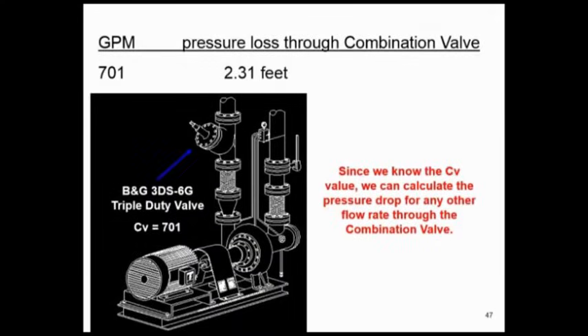So go back to my triple duty valve. The actual flow rate at 1 pound, which is 2.31 feet, is 701. So the CV of my triple duty valve, wide open in this particular case, is 701. And you can find the CV of any valve, any animal out there that you want to play with, and use that information to make a balancing valve out of it.